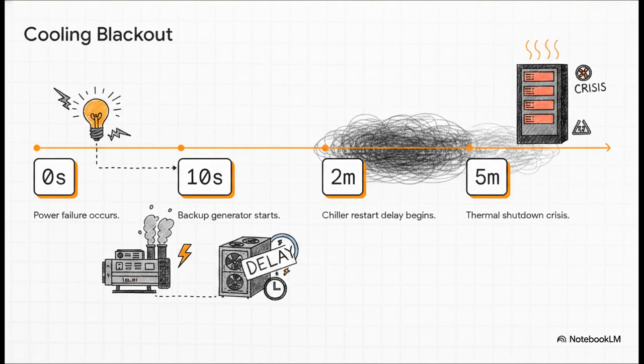And this brilliantly illustrates the massive, honestly quite dangerous gap engineers have to bridge. Let's look at the exact timeline of a blackout. Right at 0 seconds, boom, the power fails. Within about 10 to 15 seconds, those massive diesel backup generators roar to life. But even though we have power again, that chiller restart delay we talked about just started. We are now officially in a cooling blackout. By the time we hit the 5-minute mark, we're in a full-blown thermal shutdown crisis. This timeline shows us a terrifying void where the servers are just blasting out massive heat, but absolutely no new cooling is being produced by the chillers.